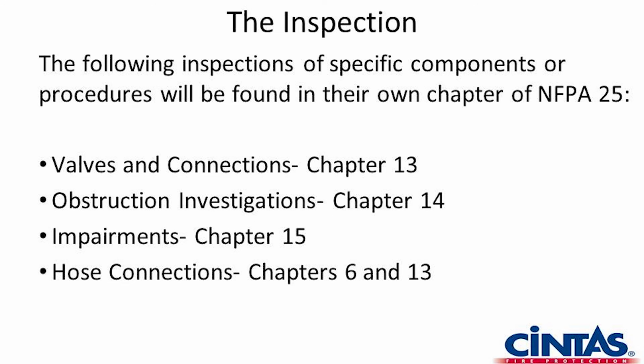Following inspections of specific components or procedures will be found in their own chapters. Our valves and our connections to sprinkler systems would be 13. Obstruction investigations, 14. Impairments, 15. Hose connections would be 6. 6 deals with standpipes. And then chapter 13 is valves. So every component within the building, in general, pipes, hangers, conditions of pipe fittings and things like that, condition of sprinkler heads, all that's going to be in chapter 5. But then when we get specific to the check valve, the fire alarm riser valve, the alarm valve, the fire department connection FDC check valve, we're going to go to 13 for the requirements for those items.